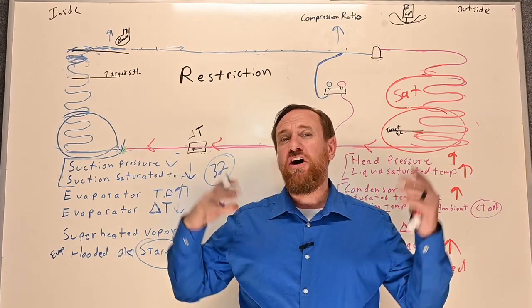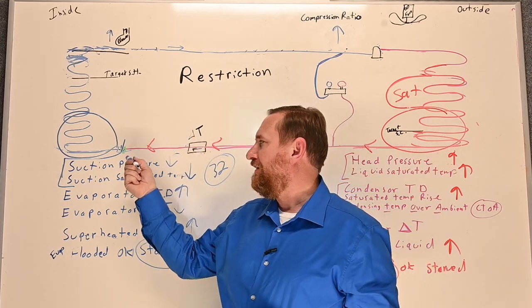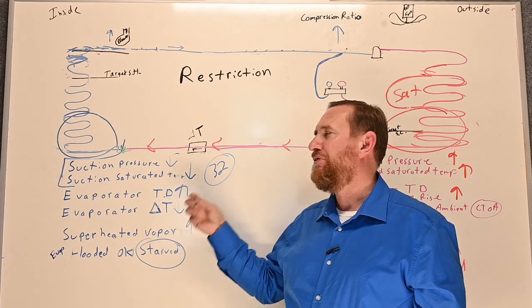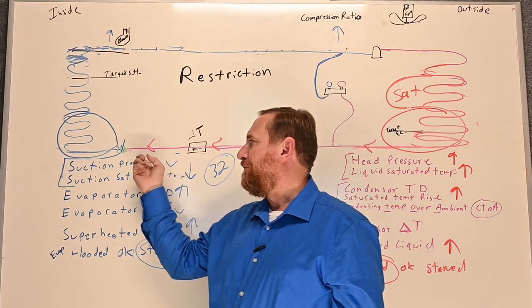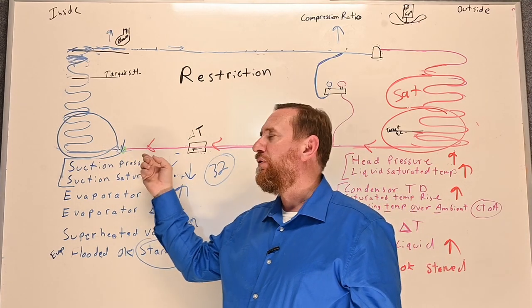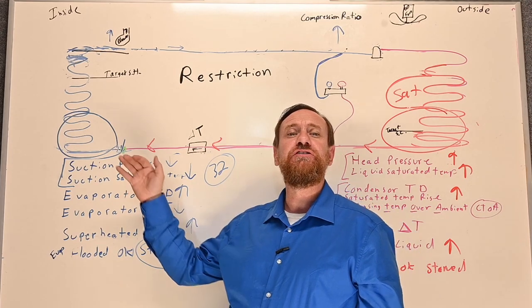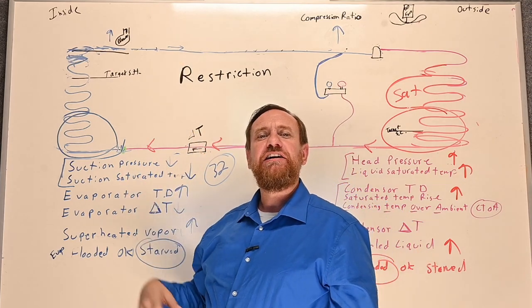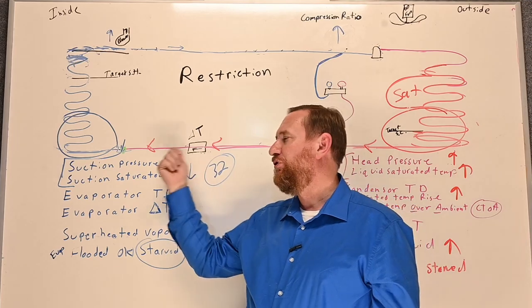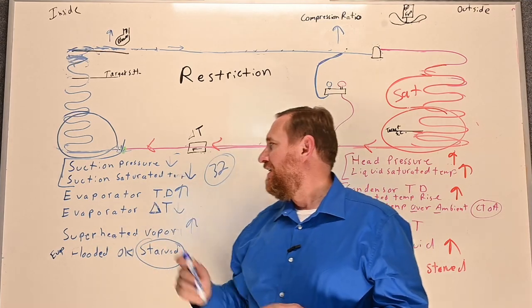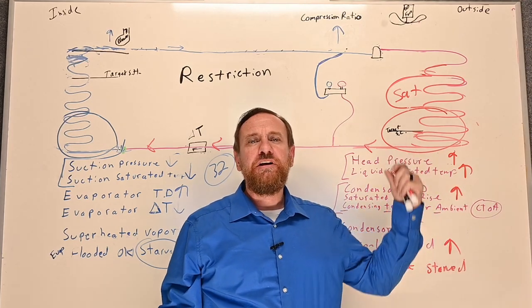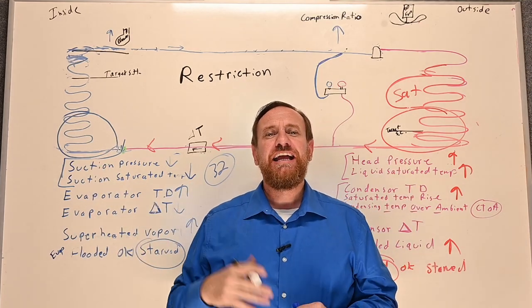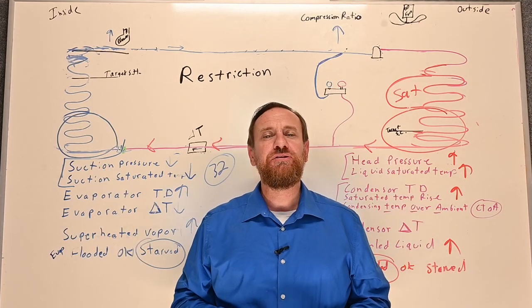All these scenarios — a too-small metering device, a TXV overheated during brazing, not brazing with nitrogen causing POE oil to clog the screen before the metering device, a damaged TXV sensing bulb, a clogged filter dryer, a valve not opened all the way — can all cause a refrigerant restriction. But also, non-condensibles can cause these same symptoms. Let's look at non-condensibles in the refrigeration cycle.